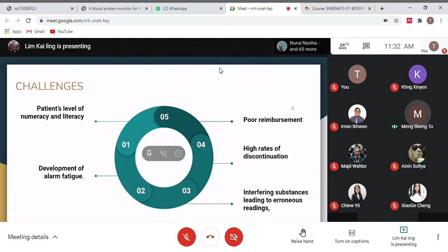Next will be the development of alarm fatigue. The CGM device is designed to alert the user to changes in the glucose level. The alarms and alerts can be programmed to sound when absolute glucose thresholds are breached or when the rate of change limits are exceeded. Most of the alarms can be silenced by the user, set to vibrate, or turned off entirely. So when an individual experiences frequent alarms, he or she may silence the alarm, change the parameters in favor of higher and lower glucose levels, or even worse, ignore them. This makes monitoring continuous glucose measurement difficult.